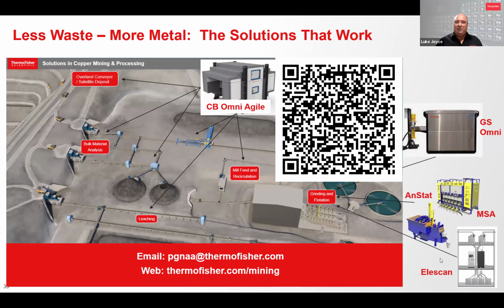I can kick off with this, I guess, the factory side of it. John's had some experience in the field, so I'll talk about the 5 Ps: proper preparation prevents poor performance. We put the work in up front in the factory calibration, which takes us weeks, and that results in an analyzer that gets delivered to site ready to go as soon as it's installed. So the on-site work is only days. Installation can take 1 to 2 days to get the analyzer physically installed. The reference standards we supply, which enable validation that the delivered analyzer is still functioning as it was when it left the factory, take a day or two. So it's a matter of days on site, and you're up and running.